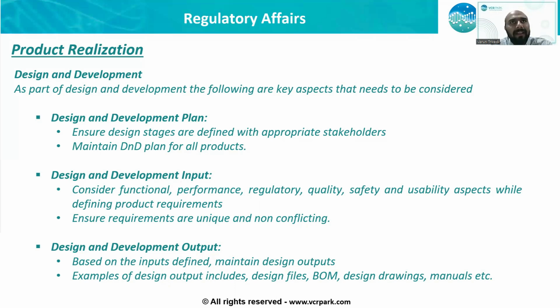And when we are defining the requirements for a device, there are 5 to 6 key aspects that we want to keep in mind. One is the functional requirements. Second is performance requirement. Third is regulatory requirements. Fourth is quality requirement. Then comes safety requirements and usability requirements. The usability is something which has developed a lot over the last few years, and now it is a mandate for any medical device organization to ensure that their product is developed keeping the usability requirements also in mind.